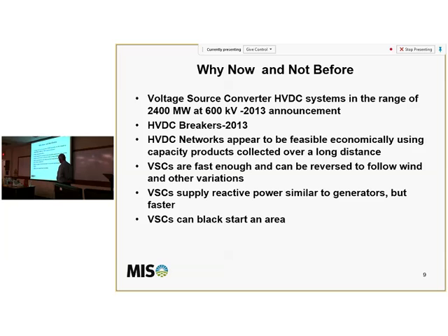The other thing is economics. DC lines are lower in cost over long distances than AC lines, and VSCs are fast enough to be reversed to follow wind and other variations. The present line-commutated DC systems take anywhere from about 30 seconds to maybe a couple of minutes to reverse, and that's too slow. So the VSC is the technological advance that makes it possible to build these networks.